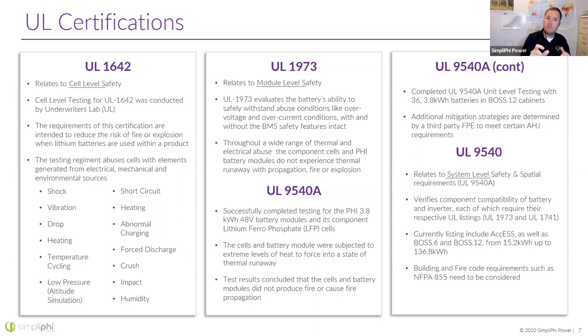Now, you definitely have to consider those rules because a lot of jurisdictions are going to be looking at that. But if we showed that we had a safe test at 9540A with our cabinets only 12 inches apart, with only an 8-foot ceiling, only 12 inches away from a wall, we're able to show in the 9540A that we were safe. That dictates what we call out in our 9540 listing and also in the installation instructions that we send with the batteries.